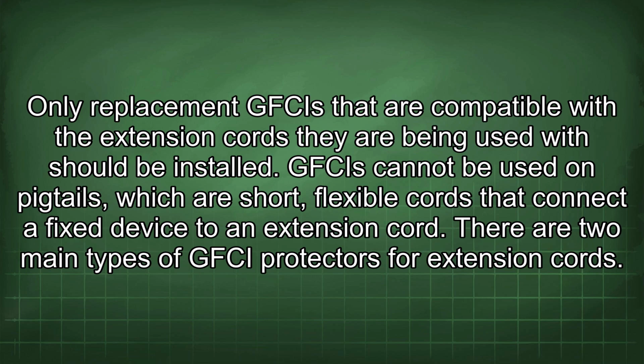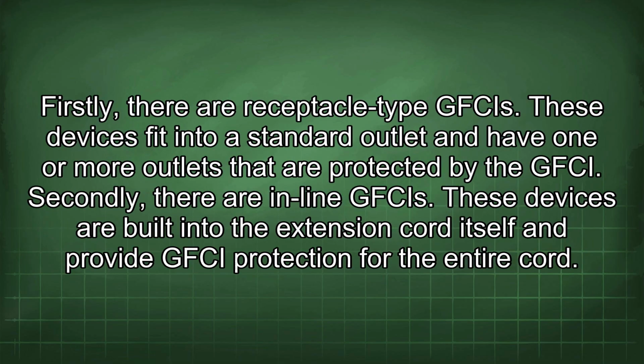There are two main types of GFCI protectors for extension cords. Firstly, there are receptacle-type GFCIs. These devices fit into a standard outlet and have one or more outlets that are protected by the GFCI. Secondly, there are inline GFCIs. These devices are built into the extension cord itself and provide GFCI protection for the entire cord.